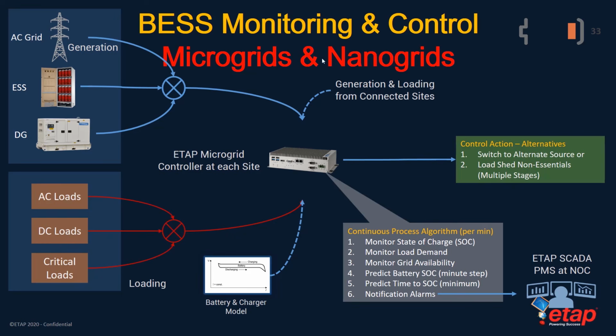So BESS monitoring and control is part of ETAP microgrid and nanogrid solutions, where we utilize a microgrid controller or a nanogrid controller at each site to essentially bring in data from the power grid, the energy storage system, any diesel generators. We bring in generation and loading from any other connected sites that may be part of the same subsystem, or they might be related to this particular site. We also bring in information from the loads such as the AC, DC, and critical loads. The controller includes the battery charger model that we have designed and developed in ETAP, and it is included as part of the microgrid controller.